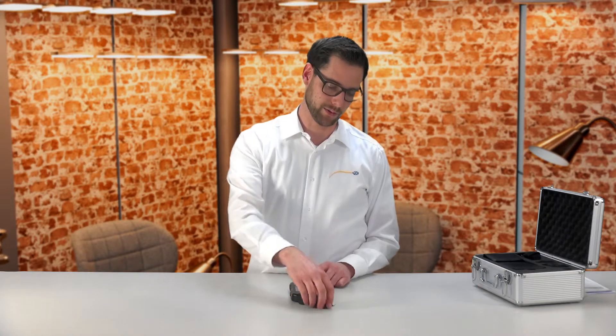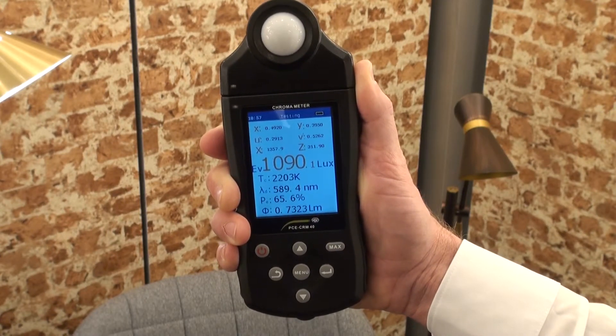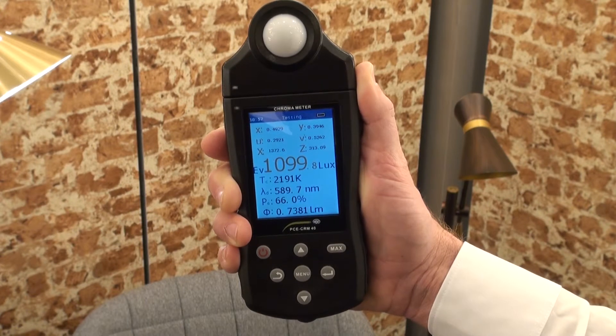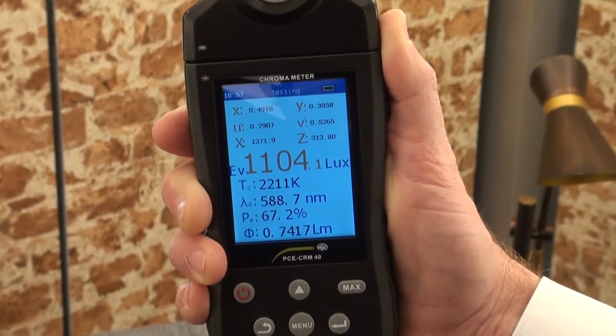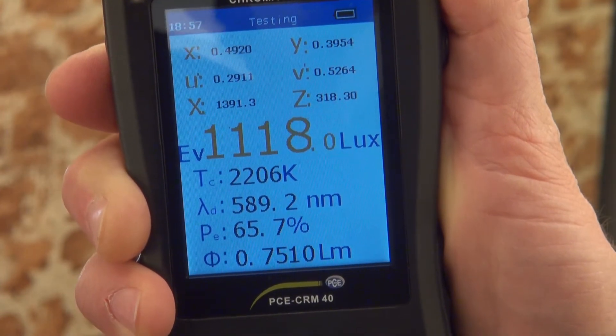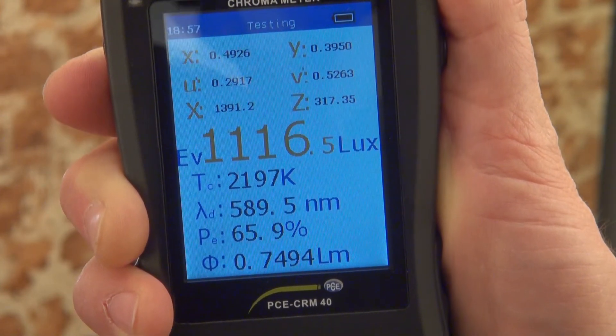In the top area of the PCE-CRM40 we have the light sensor, which is protected with a protection cap. When we turn the device on, a short start screen is shown, and directly all measuring values are displayed. The illuminance strength is shown in standard in lux, as well as the color temperature, the actual wavelength of the light, and also the tristimulus values X, Y and Z.